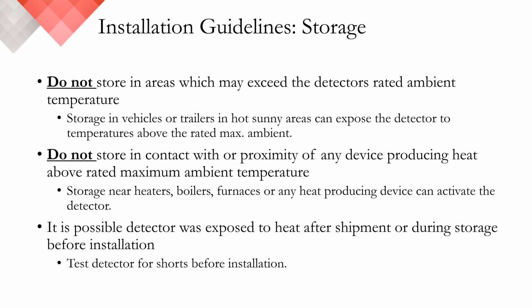When it comes to storing your linear heat detector, there are a few areas we want to avoid to assure the integrity of your device. First, do not store the detector in any areas that may exceed the detector's max ambient temperature. Each of the detectors have a specific fixed temperature rating. Along with its activation temperature, we also have a max ambient condition these can be exposed to due to the composition and physical melt temperatures of these heat-sensitive polymers. You want to be assured to avoid storing the detector in your vehicle or trailers in hot, sunny areas.